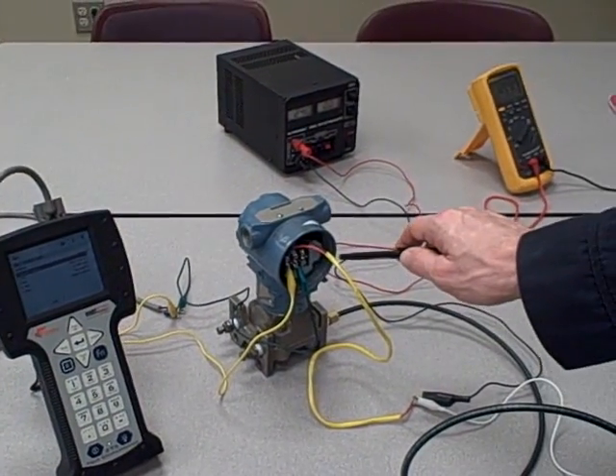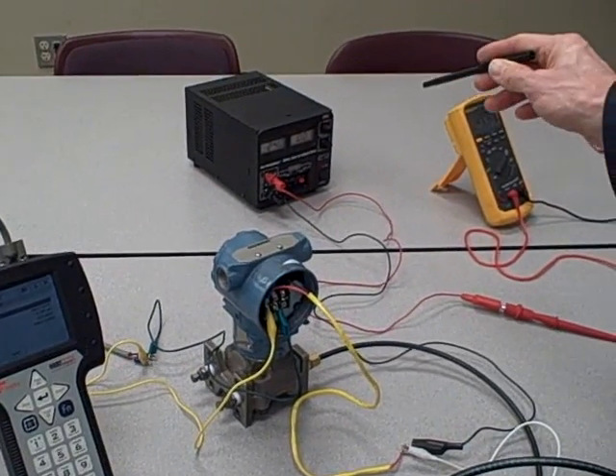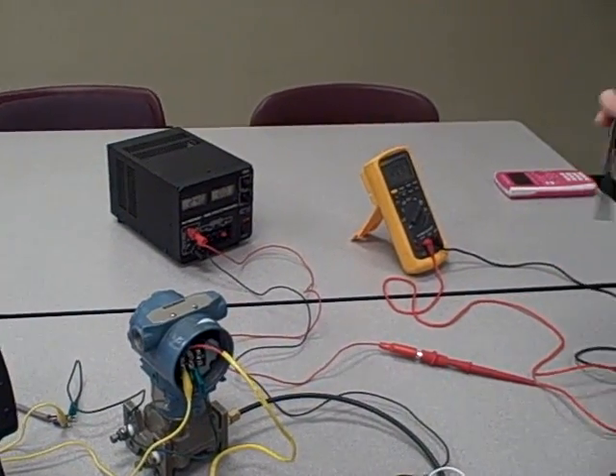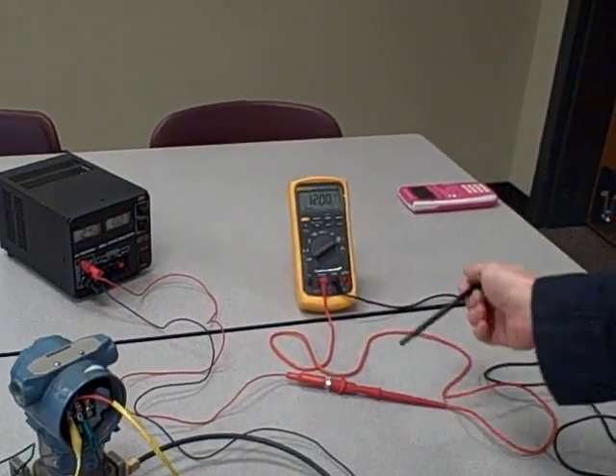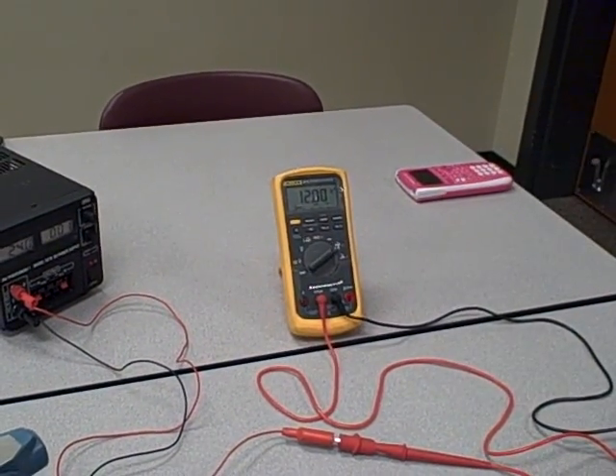Here we have a Rosemount Model 1151 Differential Pressure Transmitter. It is being powered up by a 24-volt variable supply. We are measuring the loop current using a Fluke Model 87-V multimeter, reading about 12 milliamps right now.